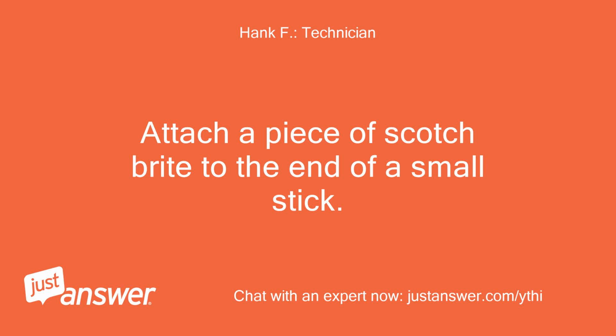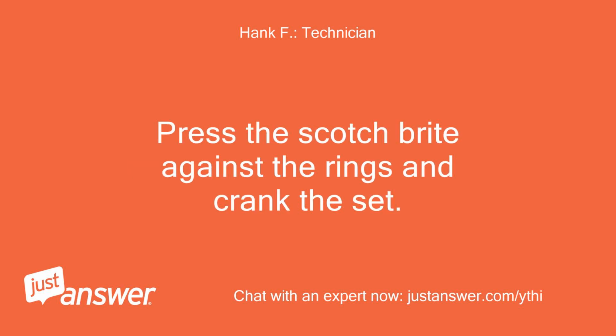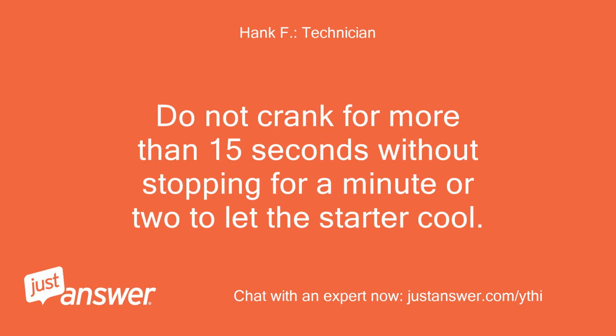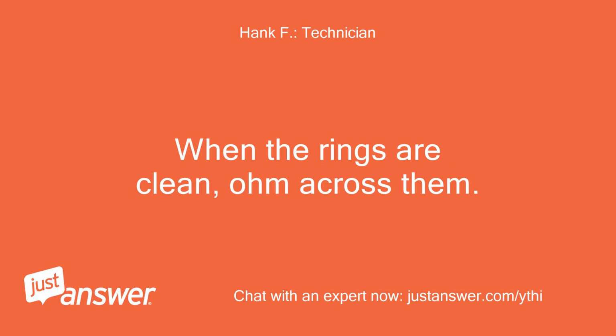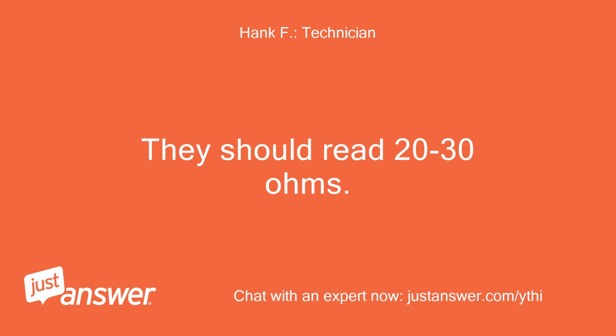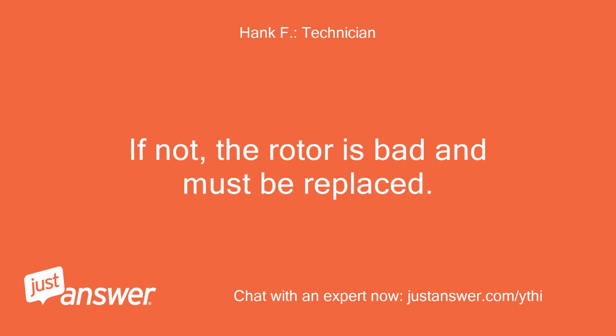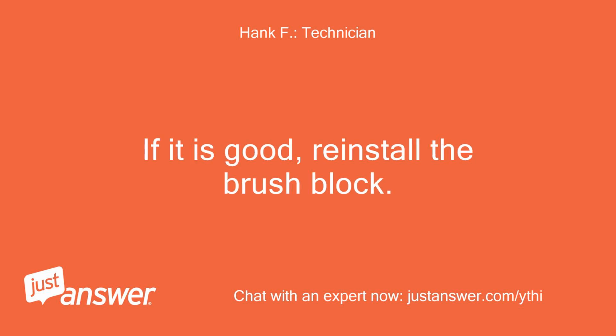Attach a piece of Scotch-Brite to the end of a small stick. Press the Scotch-Brite against the rings and crank the set. Do not crank for more than 15 seconds without stopping for a minute or 2 to let the starter cool. When the rings are clean, ohm across them. They should read 20 to 30 ohms. If not, the rotor is bad and must be replaced. If it is good, reinstall the brush block.